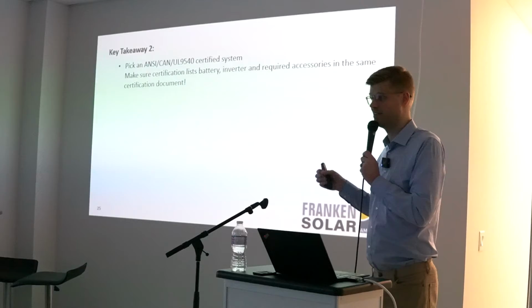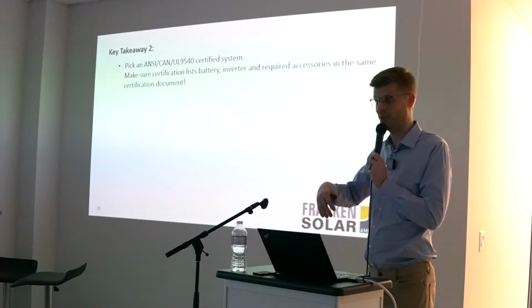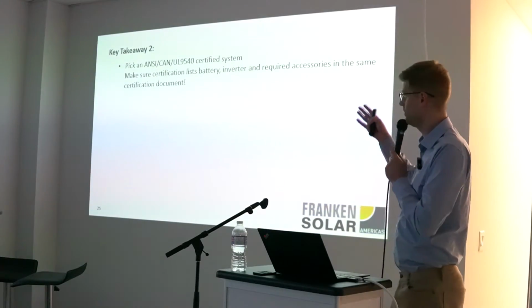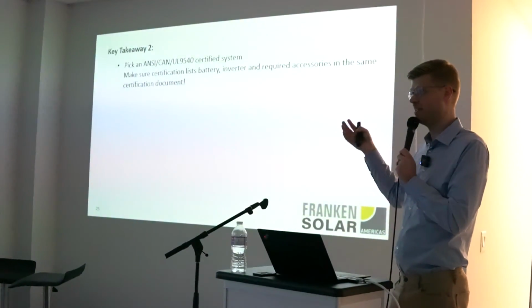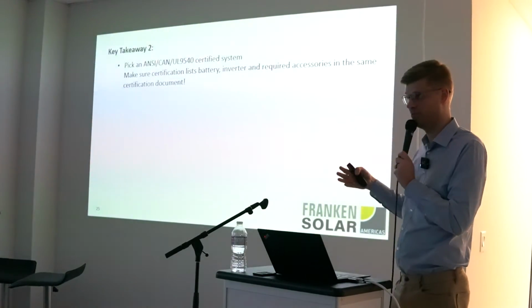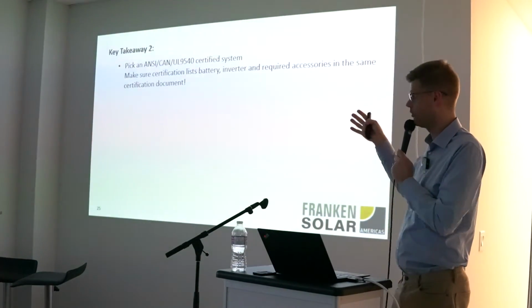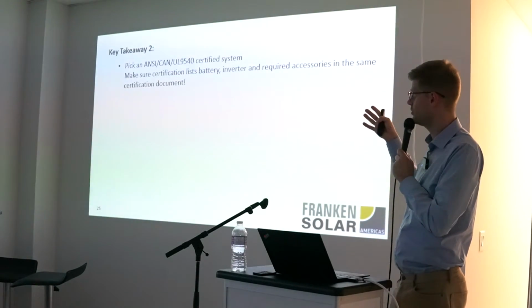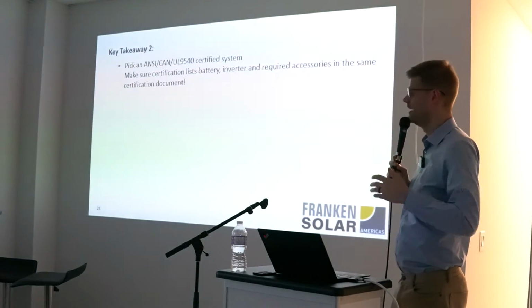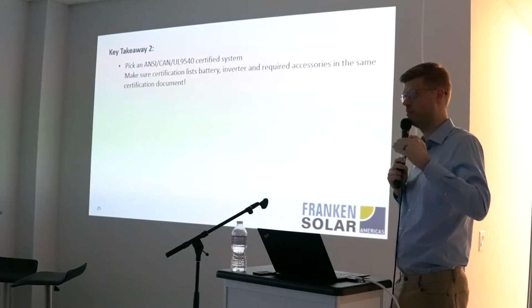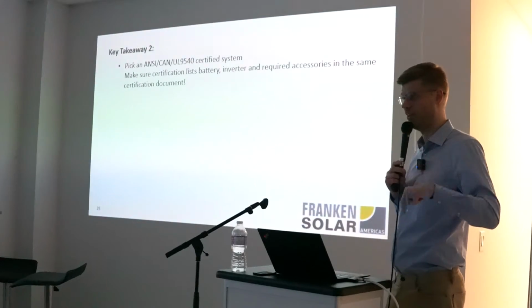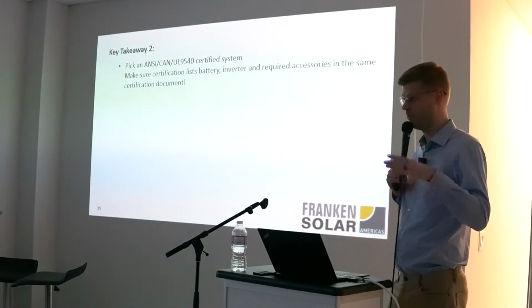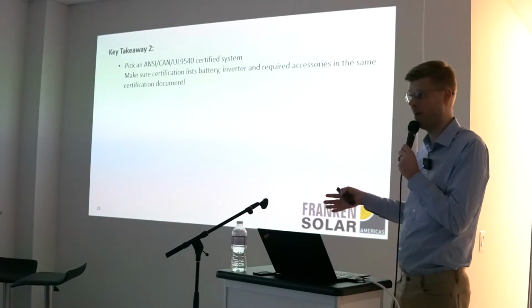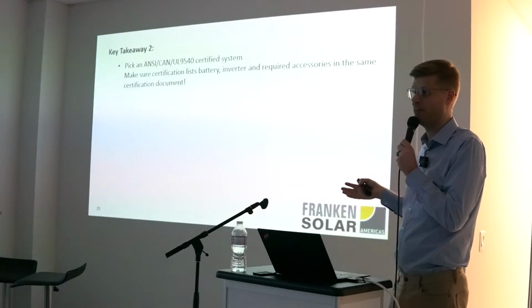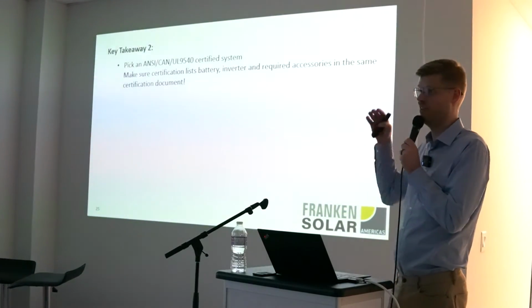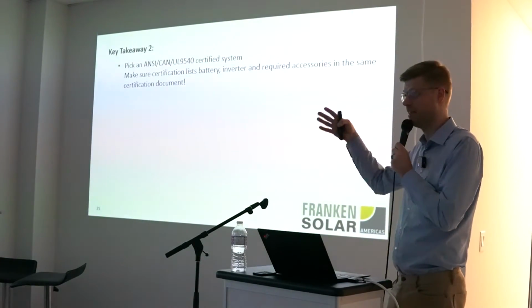There are some manufacturers that only test their battery and only test the cabinet to a former standard. For example, the UL 9540, there was a standard in 2016 that you could certify a system to on its own. But the newest and current version you have to have it certified to is the 2020 version of 9540, if I'm not mistaken. And that includes that all components have to be listed and all components have to be tested with each other. So you cannot just use, I don't want to use the name of the brand, but they have a cabinet and their own batteries and they say their cabinet and battery is UL 9540 certified. That doesn't exist, because the inverter is not specified that goes with that cabinet plus battery system.